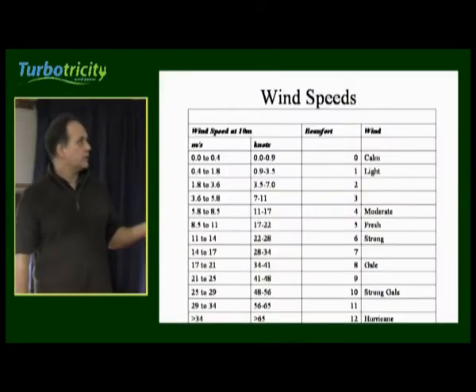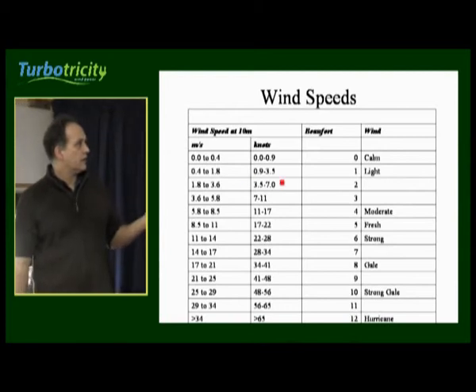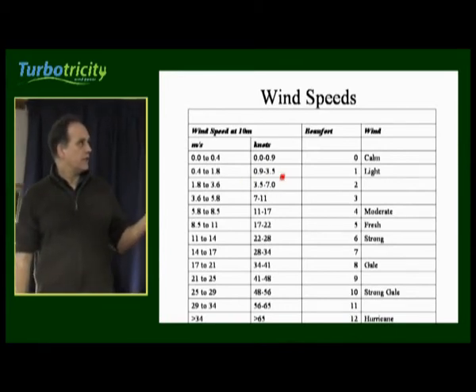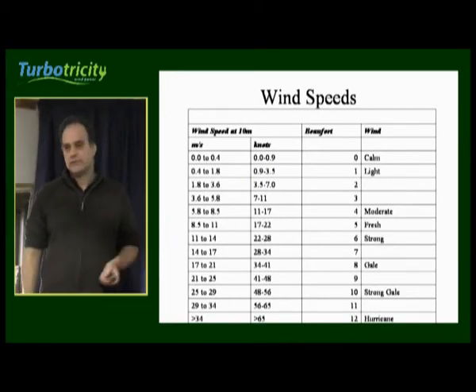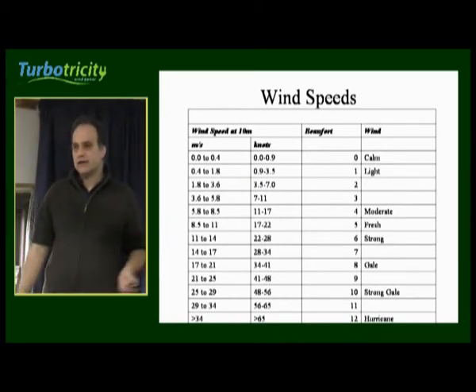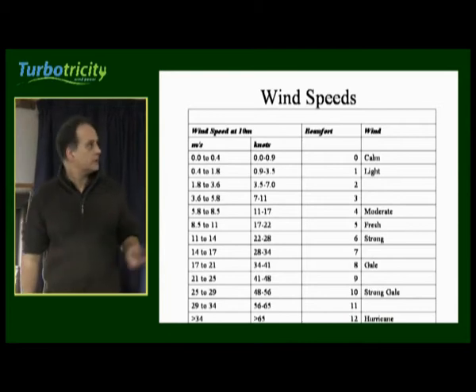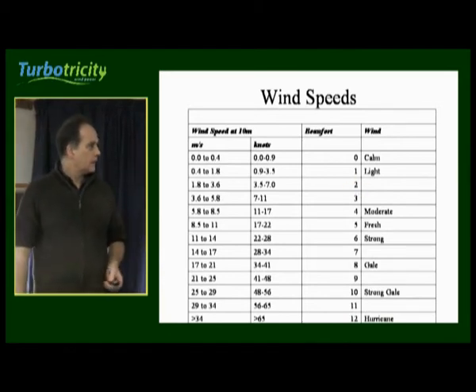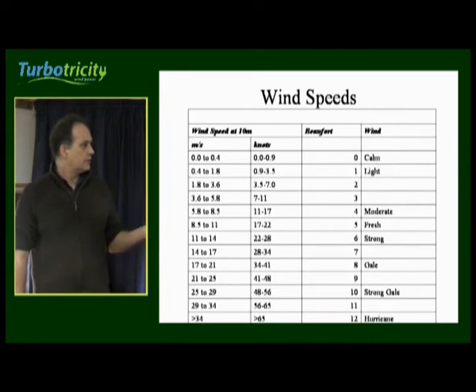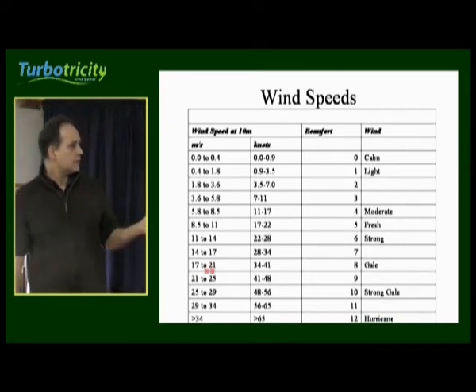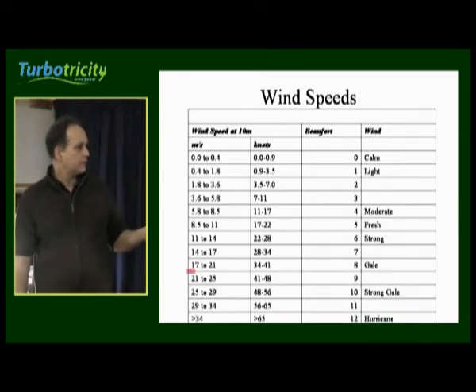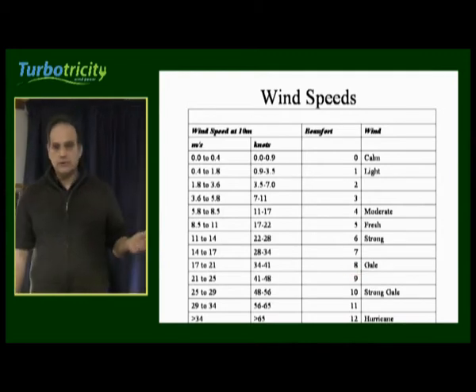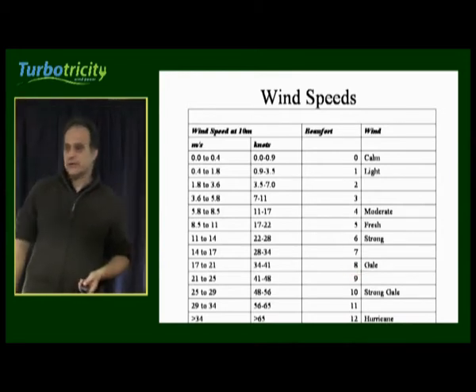Most turbines start spinning and producing useful electricity at between three and three and a half metres per second, which would be the upper end of Force 2. And a lot of turbines will cut themselves out at a wind speed of between 17 and 21 metres per second, which is Gale Force 8.